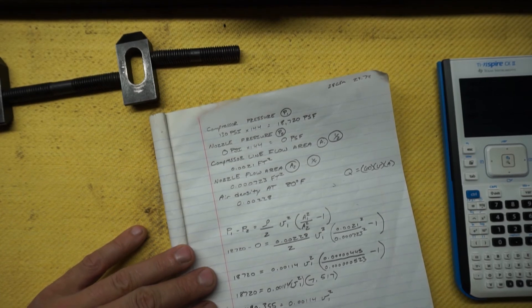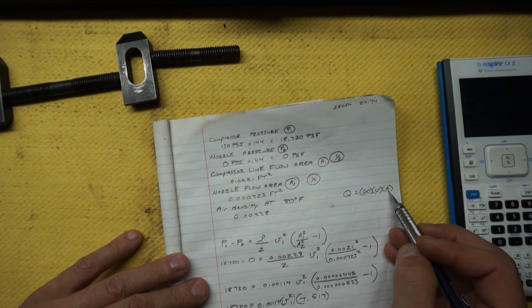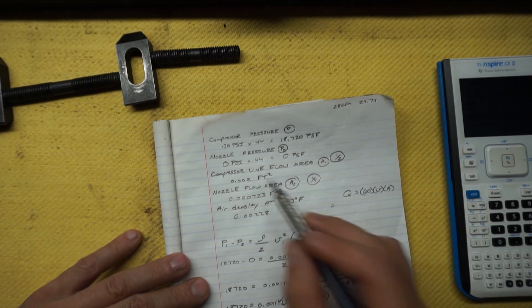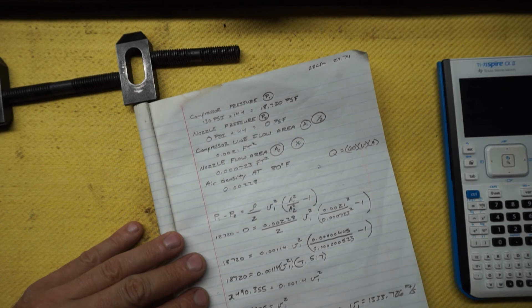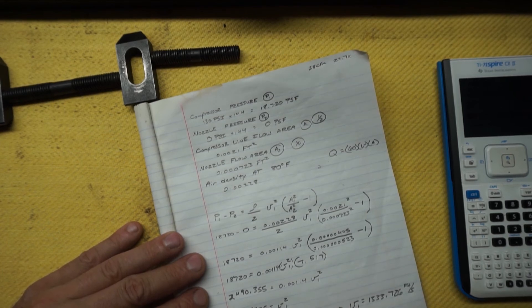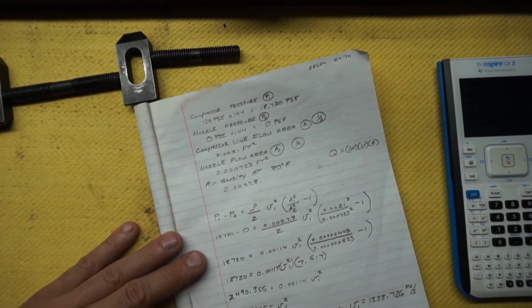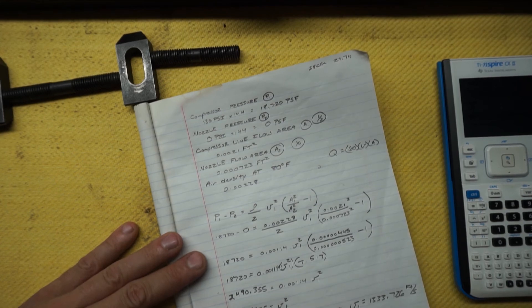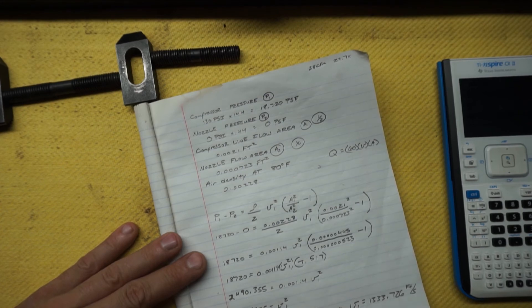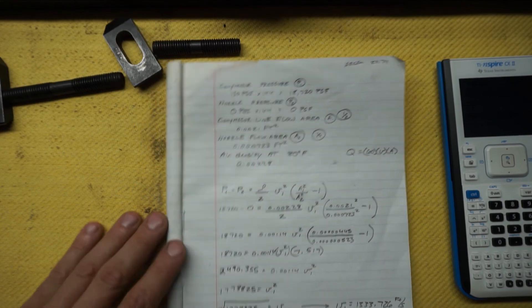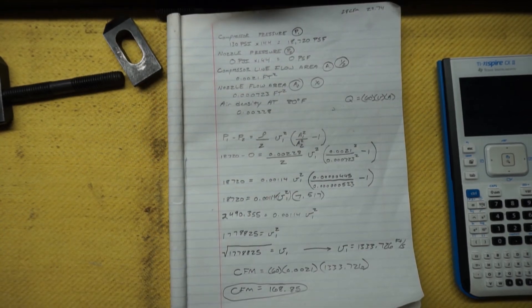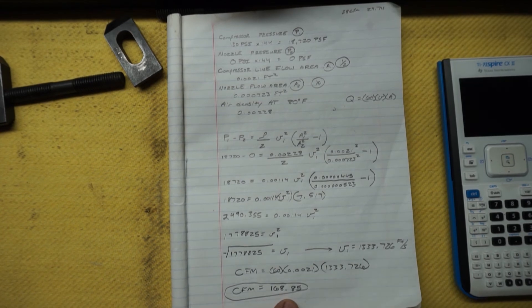But now we need CFM. Remember like up here, we know the area at the compressor, which is the 0.0021. So we got 60 seconds to convert, we got the area which is 0.0021, now the velocity 1,333.726 feet per second. Now we multiply all those together. We get CFM equals 168.85. And that is the required CFM from the compressor that you always have to have, always. Once you have that, you're all set.